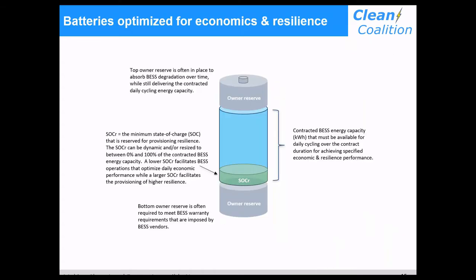Another concept I want to go through is the way batteries need to be operated. A lot of people think of a battery - somebody tells them, you've got a megawatt hour battery, and they go, fantastic, I get to use a full megawatt hour of battery capacity. But what's kind of hidden behind the scenes is that you generally have some reserve at the top to accommodate battery degradation over the years. A typical lithium-ion battery degrades by about 2% of its energy capacity per year - not a ton, but not trivial either.